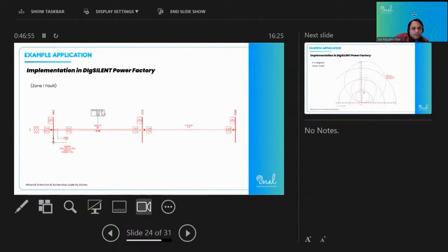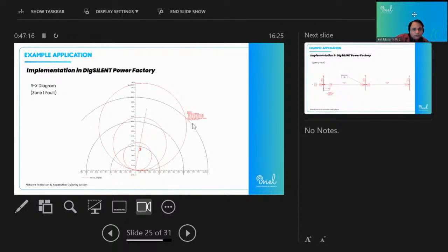So during normal load flow, this relay will be stable. Now I'm applying a zone 1 fault at this location, at 50% of the line, because zone 1 is up to 80% of the line. So this will be a zone 1 fault, and the relay will operate without any intentional time delay. You can check that this relay operates in very little time, I think a maximum of 20 milliseconds. This is the RX characteristic, which is the mho characteristic we also discussed. This is the zone 1 reach, this is the zone 2 reach, and this is the zone 3 reach. I have applied a fault which is well within zone 1, so this relay operates without any intentional time delay.